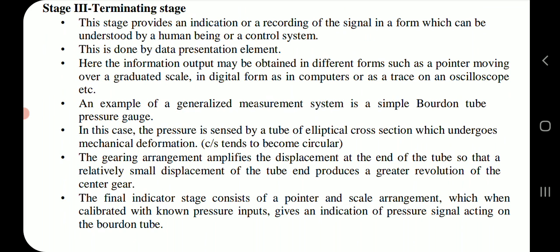An example of a generalized measurement system is a simple Bourdon tube pressure gauge. In this case, the pressure is sensed by a tube of elliptical cross section which undergoes mechanical deformation. The cross section tends to become circular. The gearing arrangement amplifies the displacement at the end of the tube so that a relatively small displacement of the tube end produces a greater revolution of the center gear. The final indicator stage consists of a pointer and scale arrangement which, when calibrated with known pressure inputs, gives an indication of the pressure signal acting on the Bourdon tube.